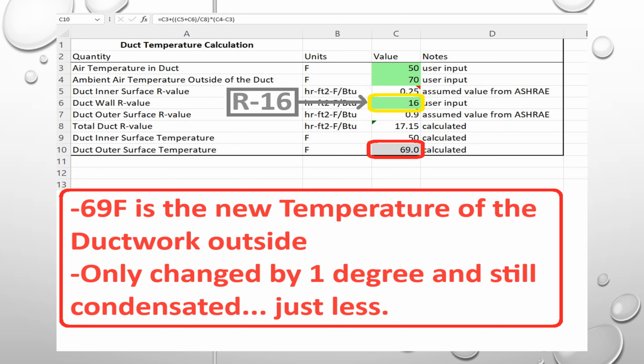The crazy part about this is I ran this through the formula, and this is what surprised me the most. We have an air temperature of 50 degrees, and we have the ambient temperature of 70 degrees, right? Those are exactly the same. But here I did the duct wall R value of R16. That used to be 8, but we ran it to 16. And the outer surface temperature only went from 68 to 69 degrees. So it only changed by 1 degree, and that's why the ductwork still ended up condensating after I did that method. So I also don't recommend doing this.